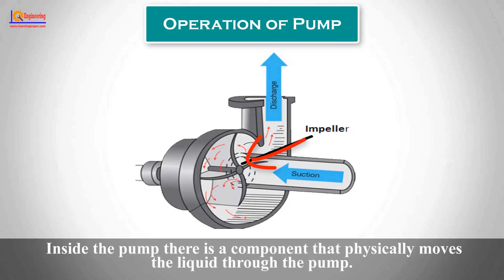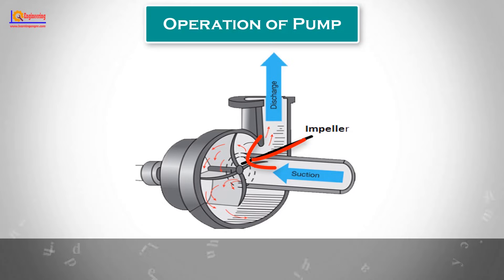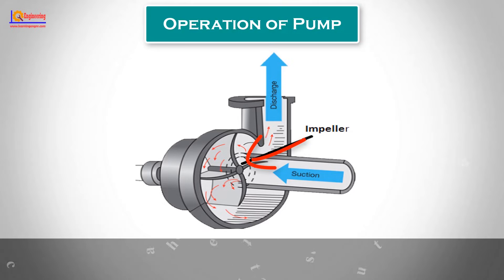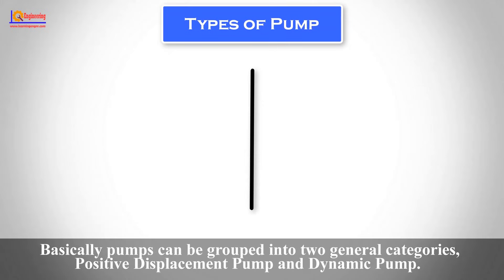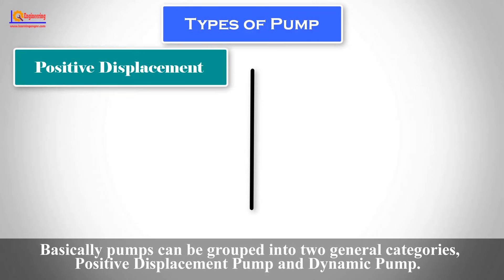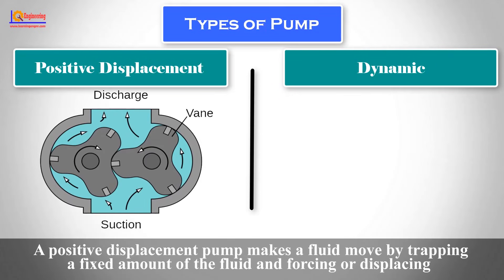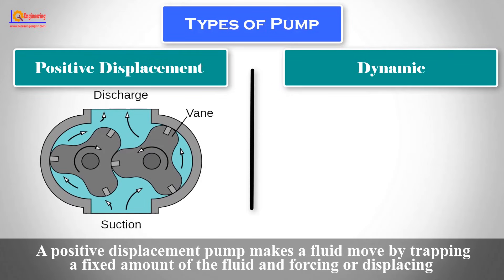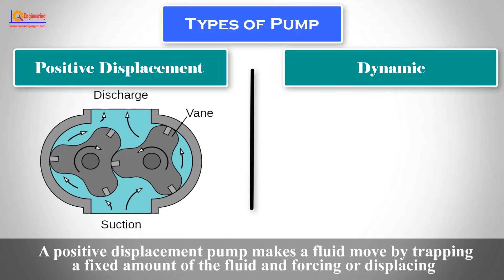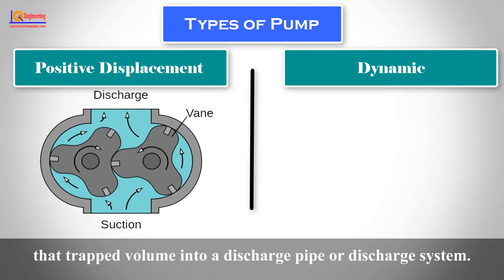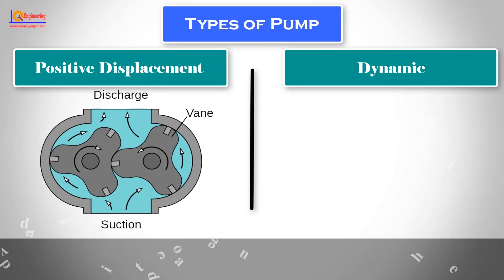Inside the pump there is a component that physically moves the liquid through the pump. The type of component used determines the type of pump. Basically, pumps can be grouped into two general categories: Positive Displacement Pump and Dynamic Pump. A positive displacement pump makes a fluid move by trapping a fixed amount of the fluid and forcing or displacing that trapped volume into a discharge pipe or discharge system.